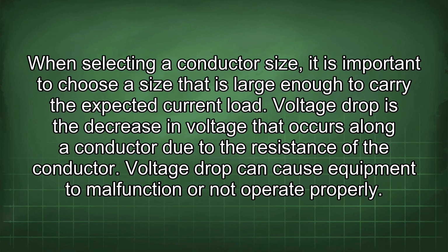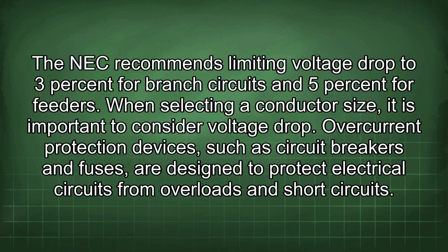Voltage drop is the decrease in voltage that occurs along a conductor due to the resistance of the conductor. Voltage drop can cause equipment to malfunction or not operate properly. The NEC recommends limiting voltage drop to 3% for branch circuits and 5% for feeders. When selecting a conductor size, it is important to consider voltage drop.